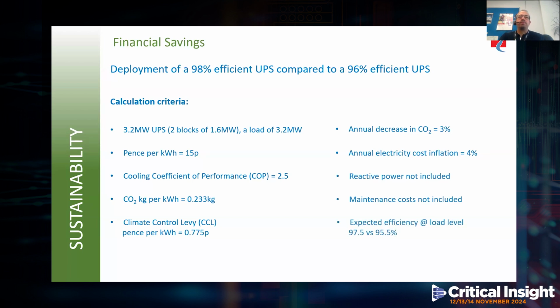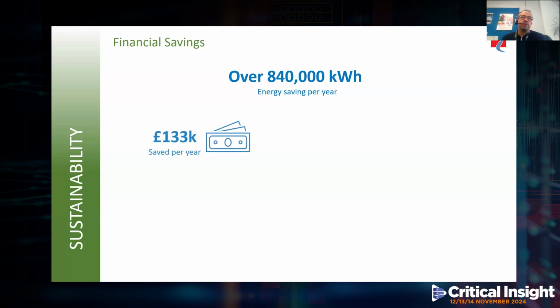And at this load level, the expected efficiency is going to be around 97.5% for the high efficiency machine, and around 95.5% for the lower efficiency machine. I hope everybody got all those numbers. So based on those numbers, the system of that type would typically provide an annual saving of around 840,000 kilowatt hours per year, which obviously equates to a saving of around £133,000 per year. And over 15 years, this results in a saving of over £2.6 million.